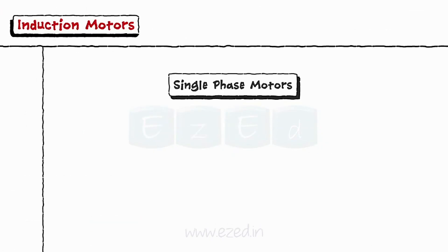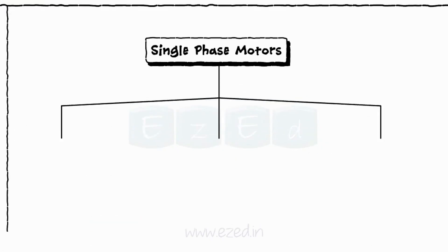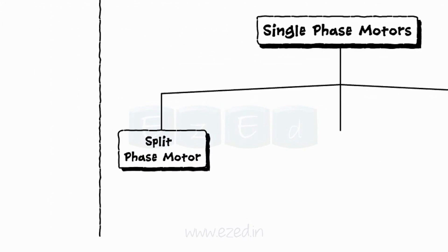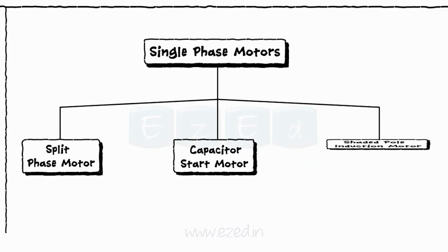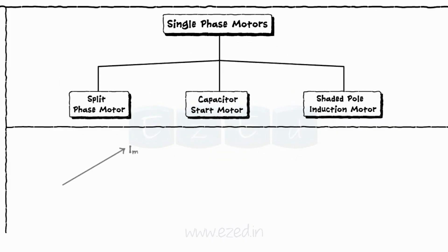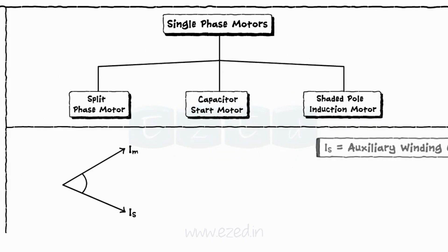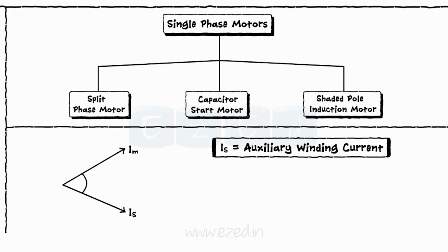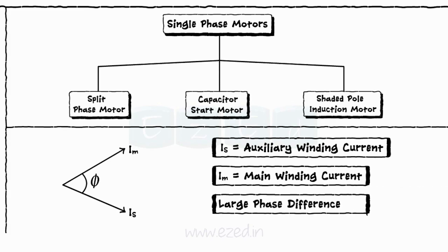There are three types of single phase motors depending on the type of winding used: Split phase motor, Capacitor start motor and Shaded pole induction motor. There must be large phase difference between the currents of auxiliary winding and main winding for the motor to act as a two phase motor.